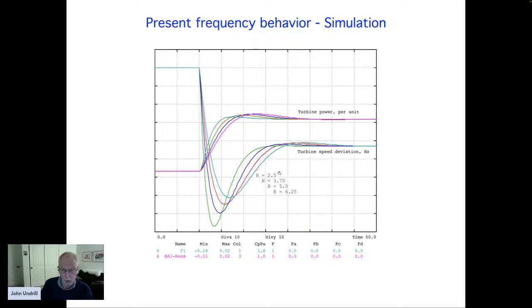If all of the machines on the grid were aeroderivative gas turbines or hydro units, you might be following the green curve here, and the frequency might have dipped down to whatever it went to. I'm not going to read the number. If you increase the inertia, you do two things. You decrease the initial rate of fall off of frequency because it's a larger mass and Newton's law of motion applies, and you slightly decrease the amount by which the frequency dips. You have an effect on the rate at which power is delivered.